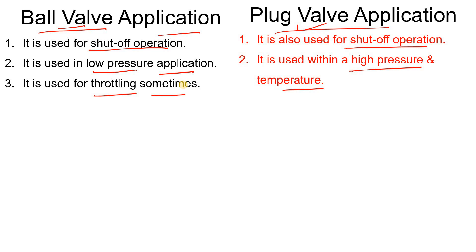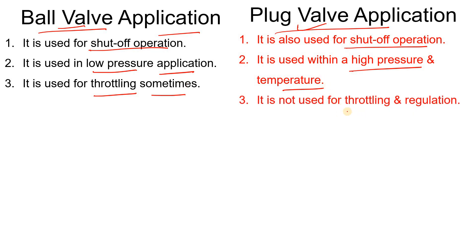Ball valves are sometimes used for throttling purposes. Most of the time, globe valves are used as control valves for throttling, but I have also seen ball valves used for throttling where high accuracy is not required. If high accuracy is required, you would use a globe valve or angle valve. But if minimum accuracy is acceptable, you can use the ball valve. In an off-site plant I have seen the ball valve used as a control valve. For the plug valve, I haven't personally seen it used for throttling, though some articles say it can be used as a control valve.